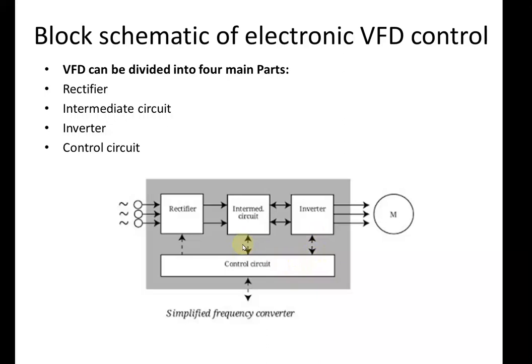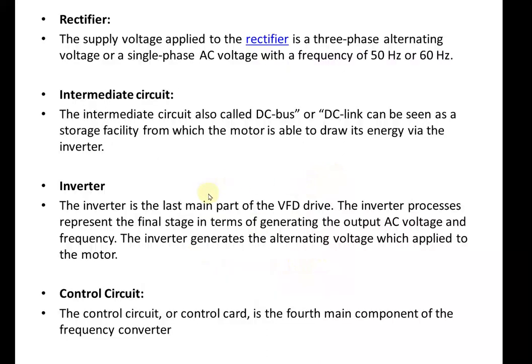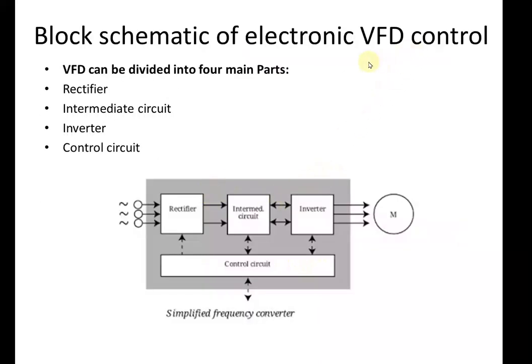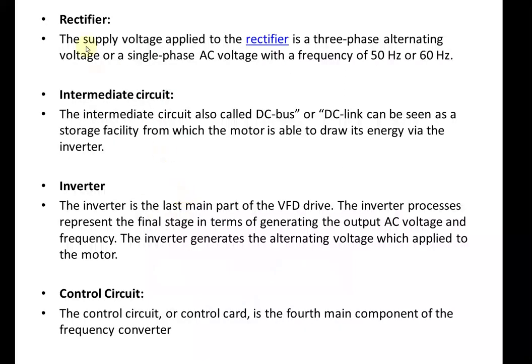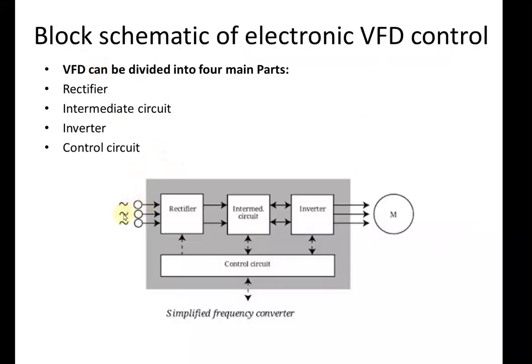The VFD is a type of motor speed controller. It drives the induction motor by varying the frequency and the voltage supplied to the electric motor. It has a rectifier, intermediate circuit, and inverter to convert AC to DC and DC back to AC. The supply voltage applied to the rectifier is a three-phase or single-phase alternating voltage with a frequency of 50 Hz or 60 Hz depending upon the region — in India it is 50 Hz.